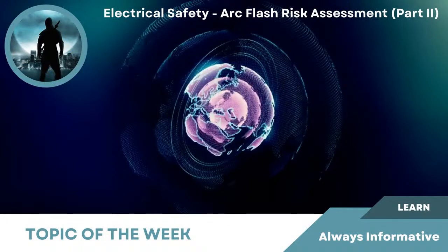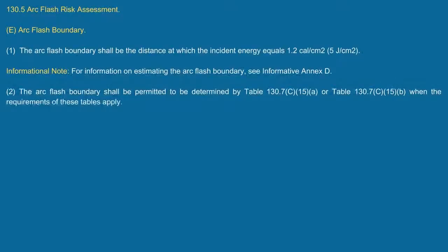This week we're going to look at part 2 of the arc flash risk assessment. We'll start with the arc flash boundary, which we looked at last week. It is the distance at which the incident energy equals 1.2 cal/cm². When estimating the arc flash boundary, go look at Annex D. If you're applying the tables, use Table 130.7(C)(15)(A) for AC systems and Table 130.7(C)(15)(B) for DC systems.